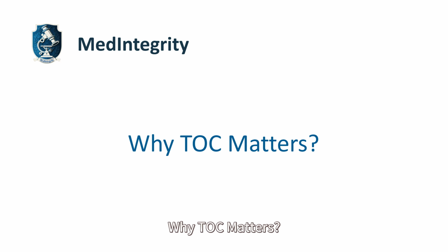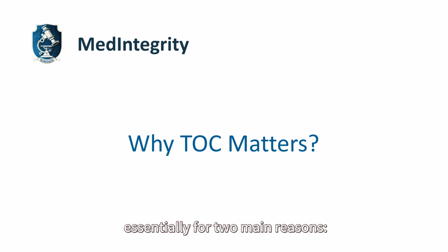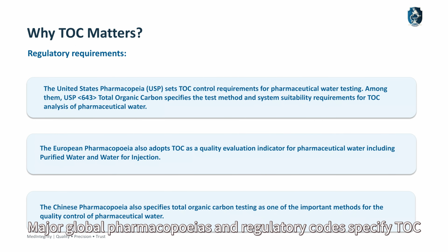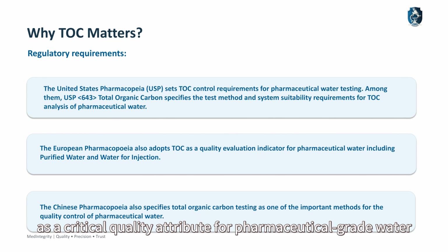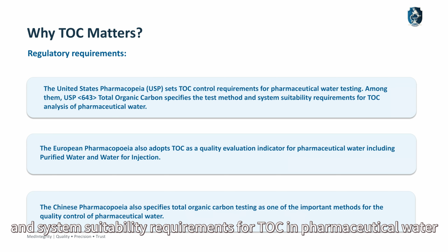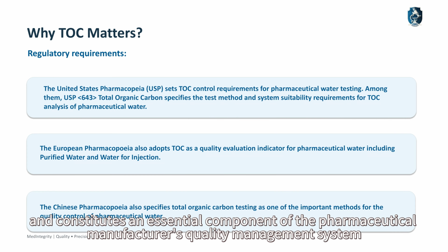Why TOC matters. The pharmaceutical industry cannot operate without TOC testing, essentially for two main reasons. First, regulatory requirements. Major global pharmacopoeias and regulatory codes specify TOC as a critical quality attribute for pharmaceutical-grade water. Pharmacopoeias, including the USP, EP, and others, specify system suitability requirements for TOC in pharmaceutical water.